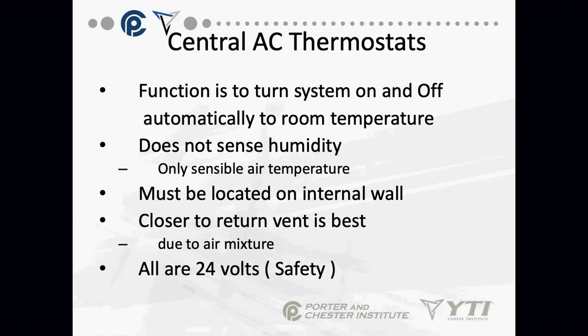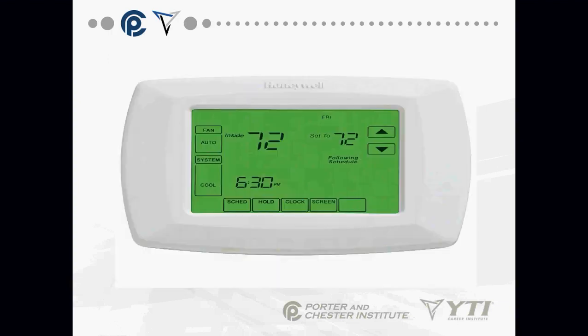All of our thermostats in air conditioning that we mount on walls are 24 volts, basically due to safety and wiring, as I've talked about before. Now, if you take apart a window unit, okay, if you take apart a window unit or a console air conditioner like you see in a hotel room, those thermostats that are in those units might not be 24 volts. You have to check, so be careful.